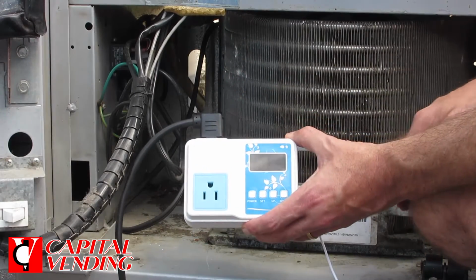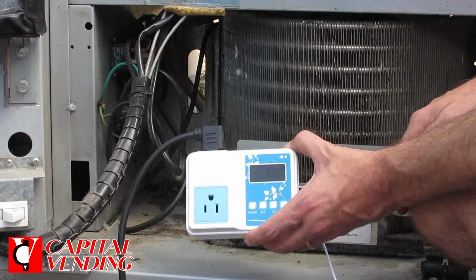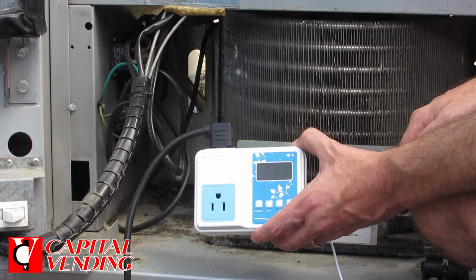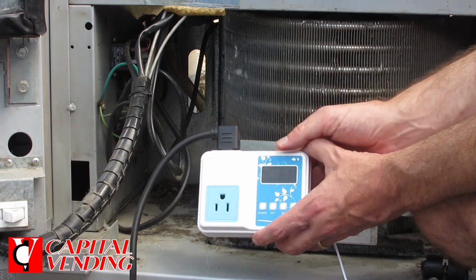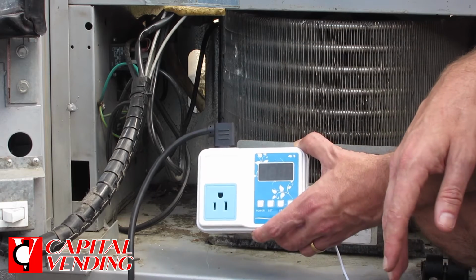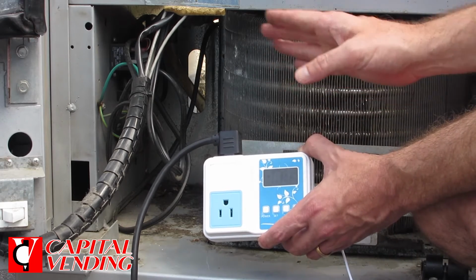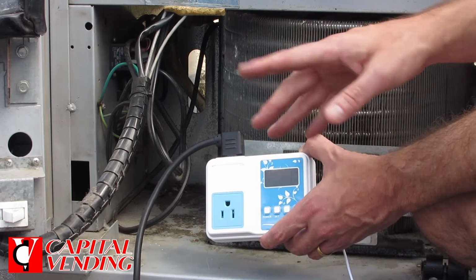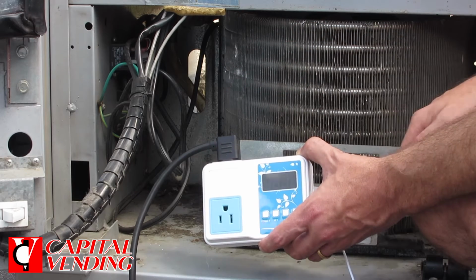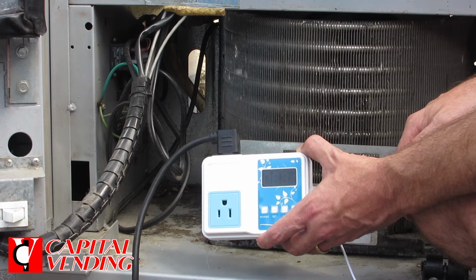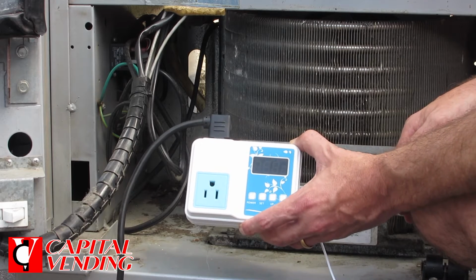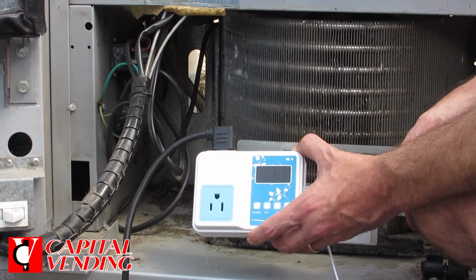In this segment, I'm going to be installing this in a Royal Vendors stack machine. This machine is controlled by a control board, so it has additional features you need to be aware of. The temperature probe, the relay, the door open switch, and the control board can make the refrigeration system seem like it's not working, so using this unit you'll be able to determine if it's actually working or not.